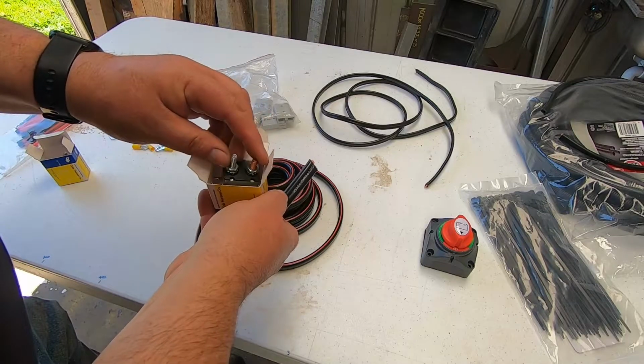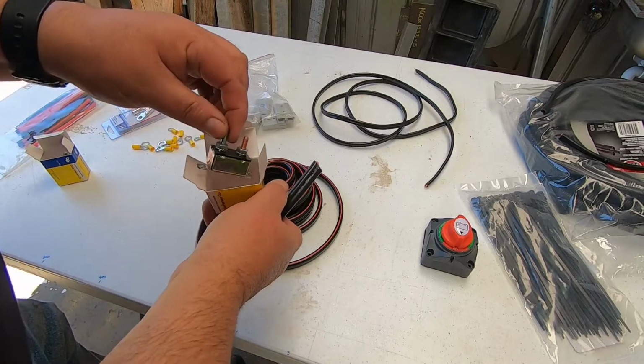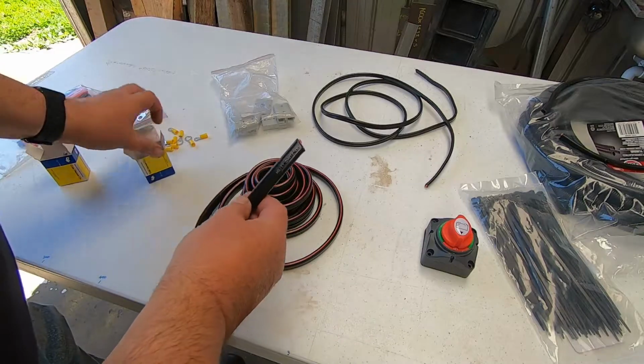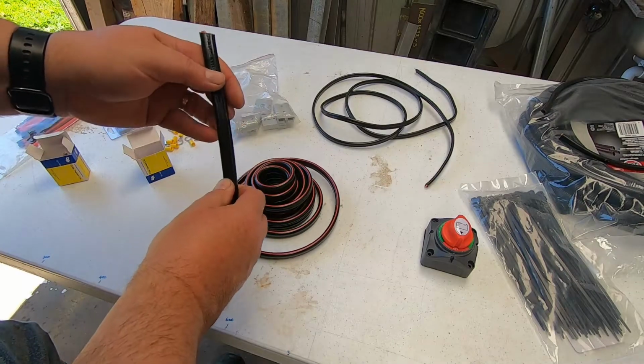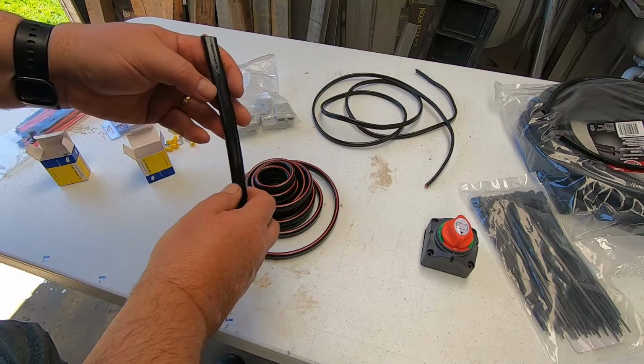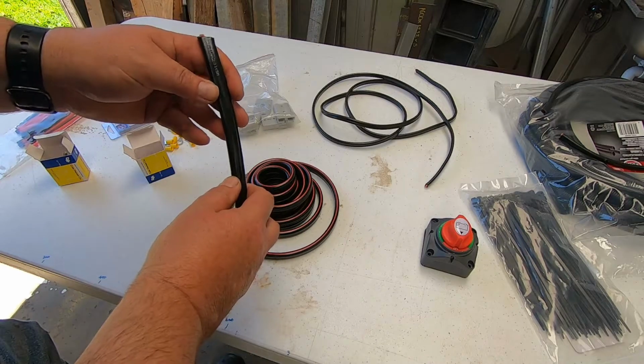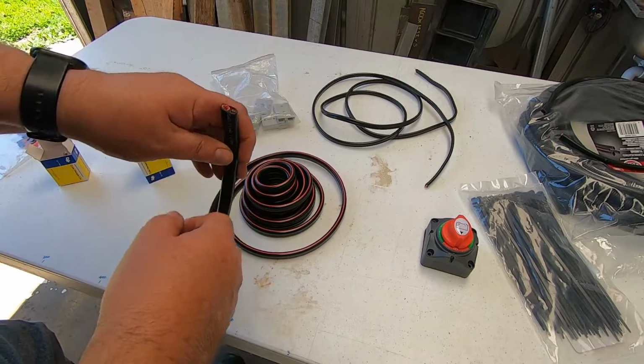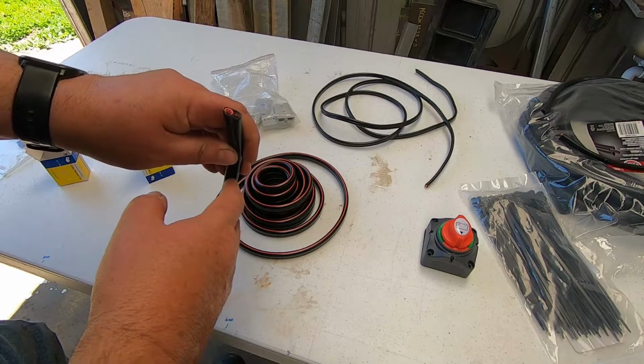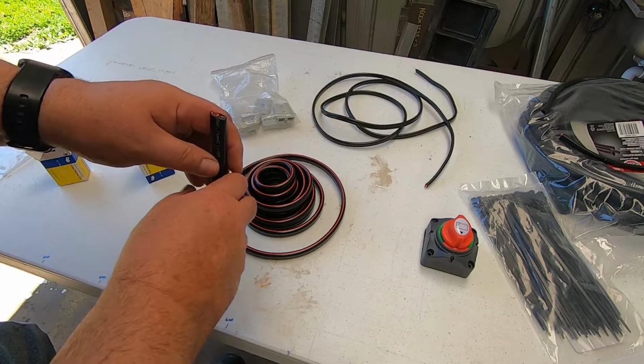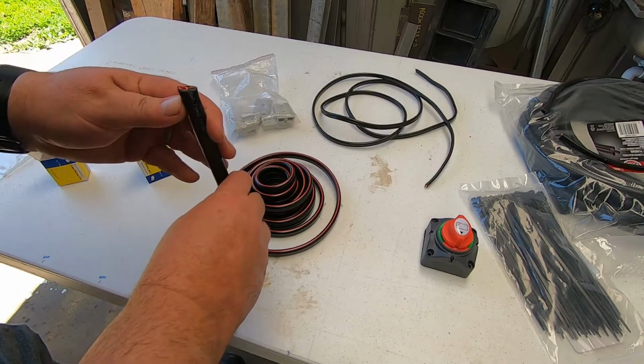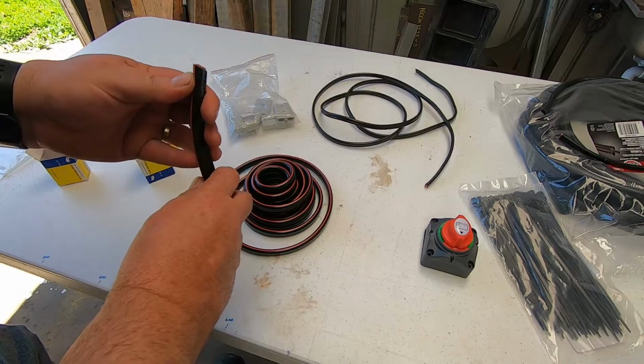If I find this trips out, which I'll be amazed if it does, I'll change it over to a slightly heavier one. This cable's rated at 100 amps apparently, but when you read it properly, it's at a 60% duty cycle for 5 minutes. So realistically it's probably only good for about 80 amps, something like that, which will be plenty for what we're doing, because this outboard electric motor, if we ever get one, I think they're rated worst case scenario at 50 amps.